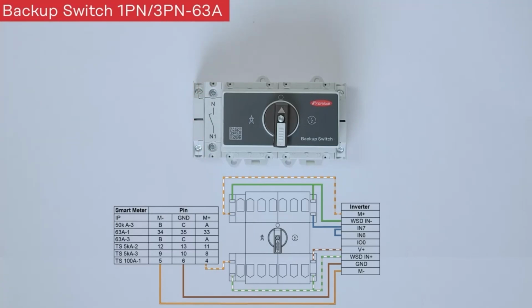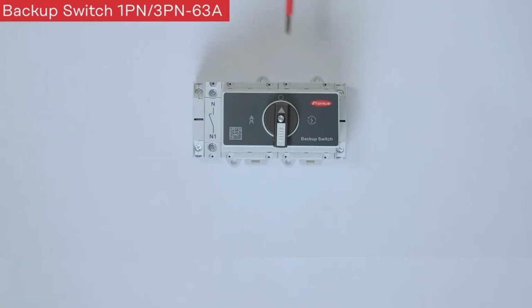To also cable I6 and I7 contact on the right hand side, on the backup position, we also now have an extra auxiliary contact, an extra auxiliary switch to connect I6 and I7. This is due to national standards and norms, because you need to cable the PEN connection double. So that means that L2 and L3 are now covered with the PEN connection.